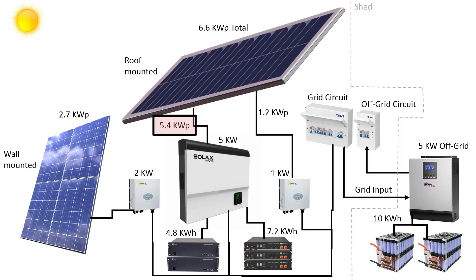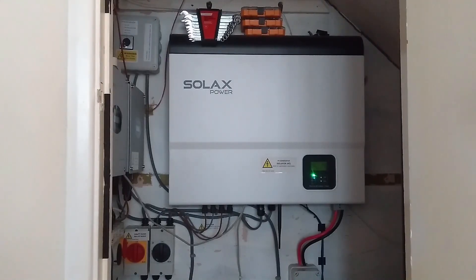There's technically 6.6 kilowatts of solar panels. This is quite normal — it's usual to oversize the panels relative to the inverters, because very often they won't be generating their absolute peak, and what you want is the inverter to be able to give you the most it can most of the time. This is my five kilowatt Solax hybrid inverter — it's both an inverter and a battery charger.